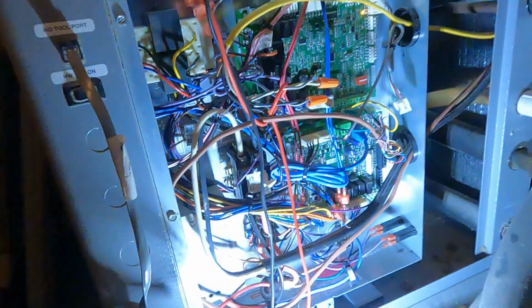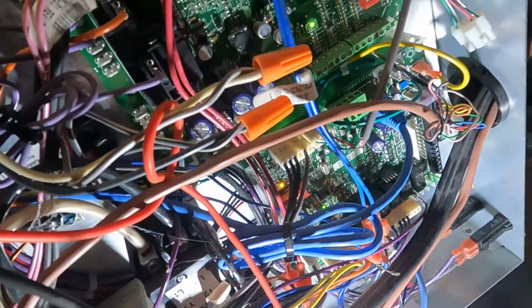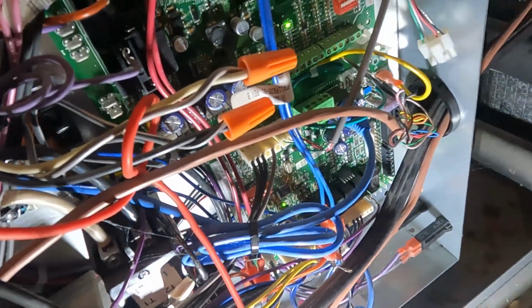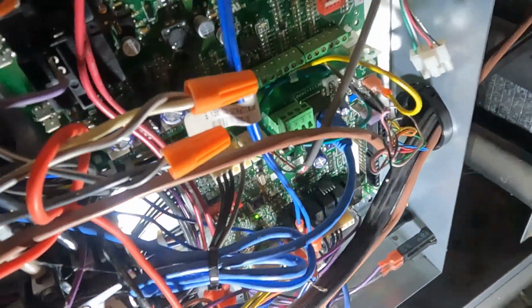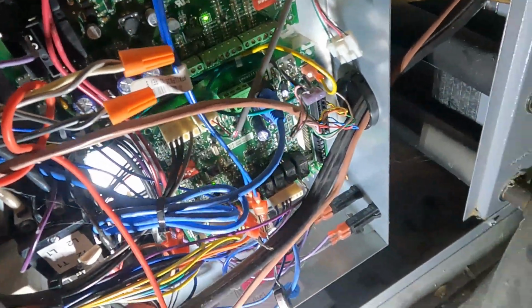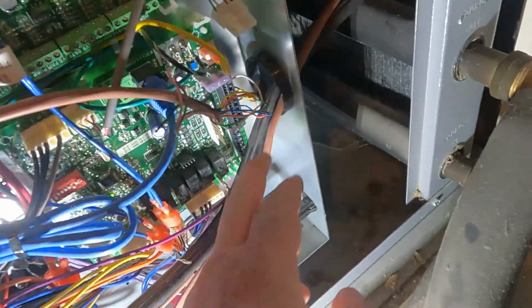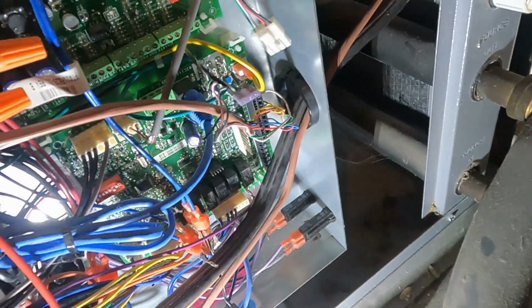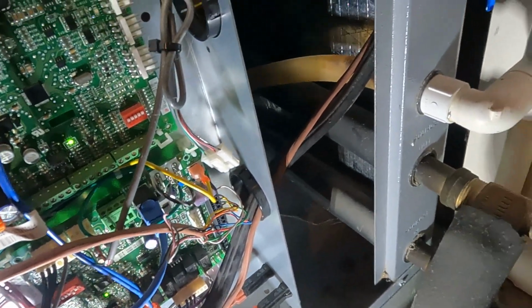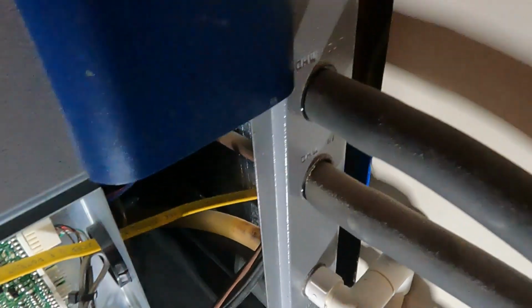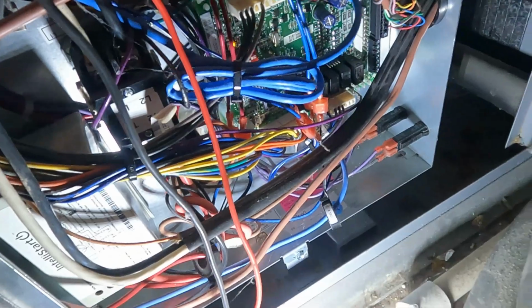What I can tell you is probably the underlying issue with communication errors on this, and I'll get it closer up here and show you. The type of thermostat wire that they used is just regular 18 gauge thermostat wire. And typically on communicating equipment, they want you to run a shielded thermostat wire. The reason is when you run it next to high voltage wires like this right here, sometimes you get a little bit of electrical interference with those communication wires. You can see that one hugs that wire, it even goes up the wall here, hugs it. So that's most likely the underlying issue with it.